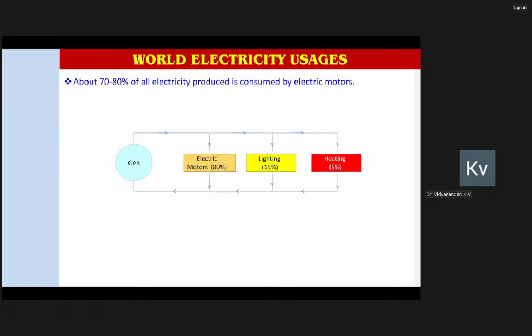Now, from the equipment point of view, why it is so important is, if you take the total individual loads we cater, around 70-75% of these electrical loads are motors. Motors means induction motors, asynchronous motors. If you take your own 600 megawatt thermal unit, the individual unit will have more than 550 motors, starting from your BFP up to a small dewatering pump of maybe 1 kilowatt or so. So around 75 to 80% is induction motors, and these induction motors have peculiar behavior.